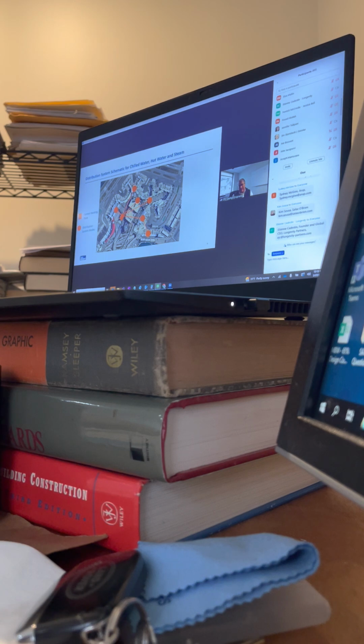This is just a schematic of where the central heating plant is and where the basic nodes are. I'll talk a little bit more in a second about what we provide to each terminal. One of the challenges you're going to find is that the oldest building in the service area is 1955, and the latest, which you'll see on here as that red crescent, is the terminal expansion that hasn't even opened yet. And we provide a variety of different mediums to heat the terminals in the service area. All of them are cooled by chilled water, but we provide steam directly to hot decks in fan rooms. We provide high temperature hot water to various different things. So there's not one system that serves everything, but generally these mediums come out of the central heating plant through utility tunnels, and they end up at these various facilities.